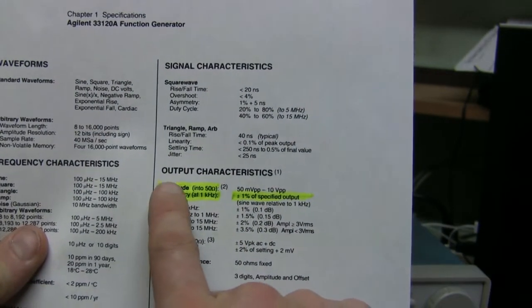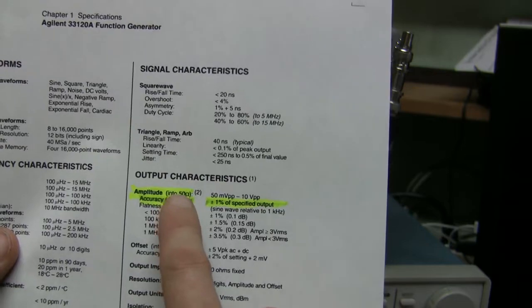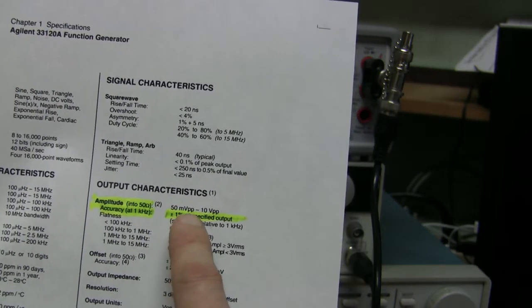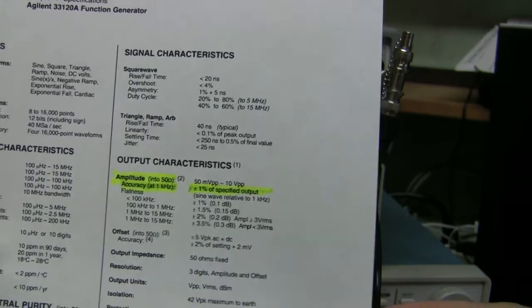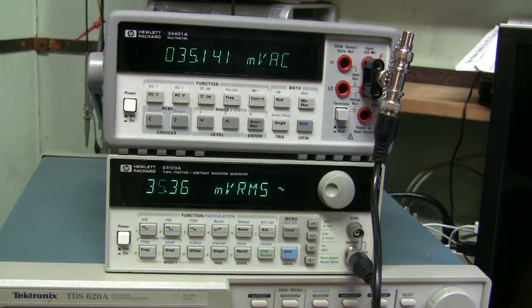I highlighted it here. Amplitude into 50 ohms accuracy at one kilohertz, that's exactly what we have. And it should be one percent of specified output. So let's plug these numbers into a calculator.